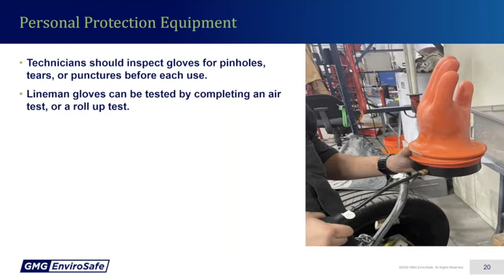Pinholes, tears, punctures, or expired gloves can result in electric shock. Do not use rubber insulating gloves that do not pass the inspection. Lineman gloves can be tested before each use by completing an air test or a roll-up test. There are inflator kits you can buy where you can place the glove on an inflator and look for any leaks passing through a damaged glove. You could also do the roll-up test where you roll the glove up until it's inflated, and then you look to see if there's any air leaking through a pinhole.